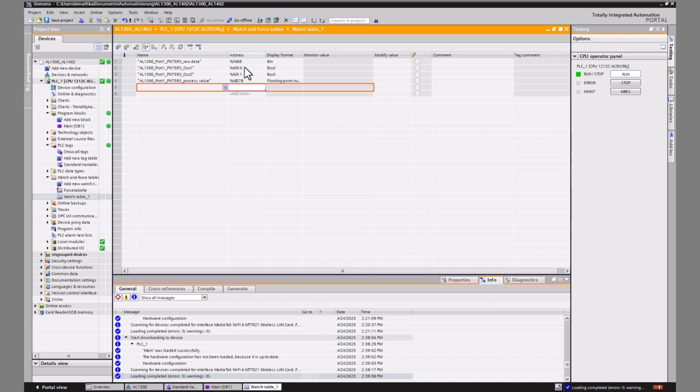As can be seen from the operating instructions, the status of the additional read-in of pin 2 is found in the first bit of the PQI. As a byte for the port qualifier information is automatically provided in the memory area we have defined for the I/O link data, we can address this directly with byte 70.